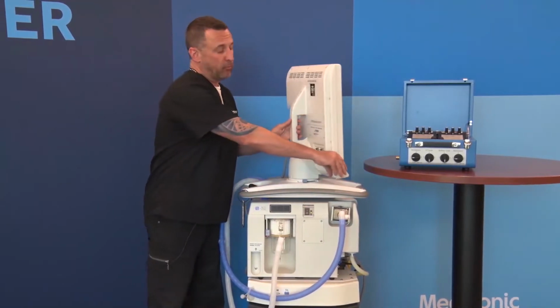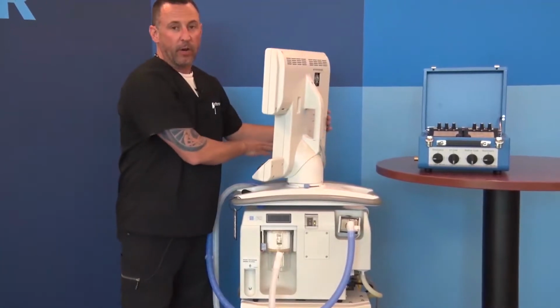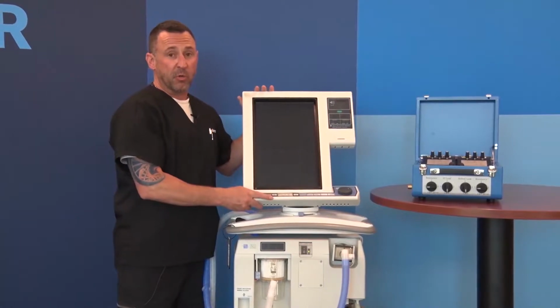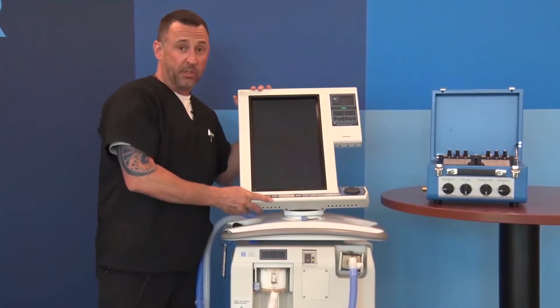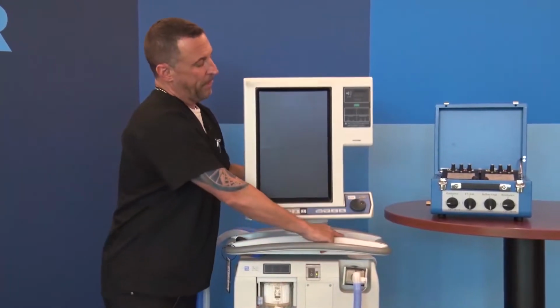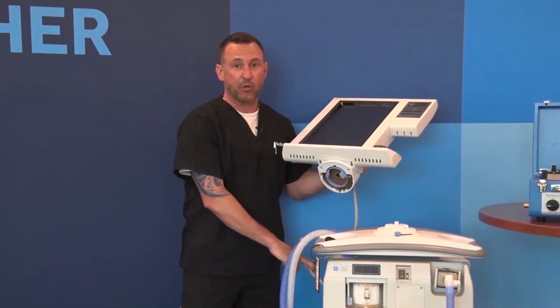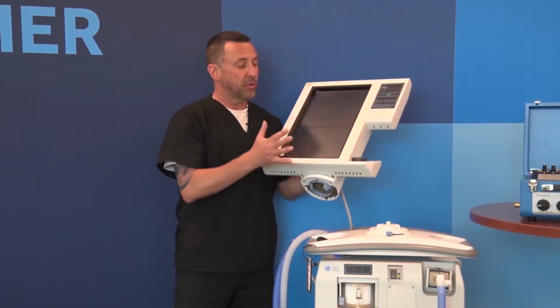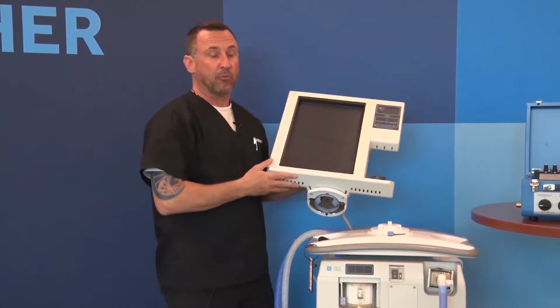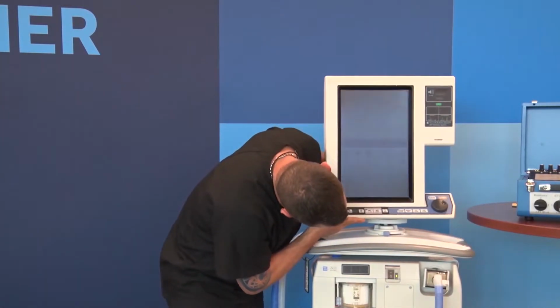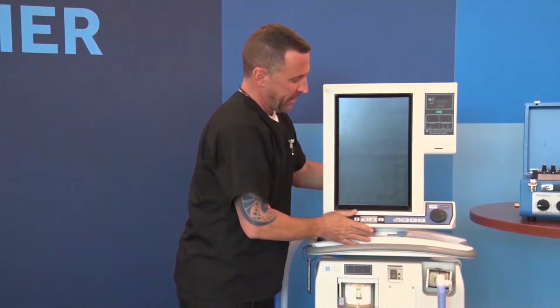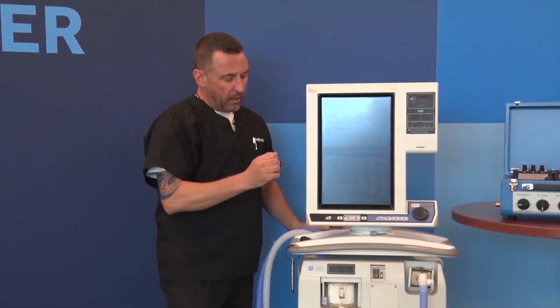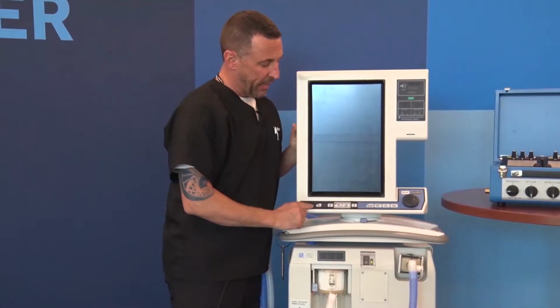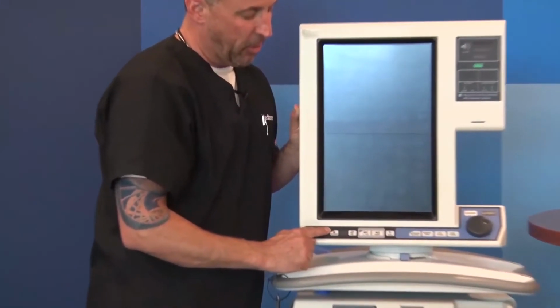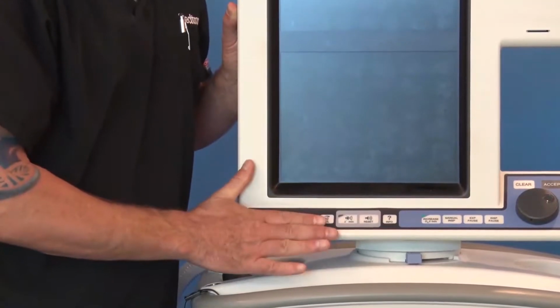The screen, it does move. It rotates 270 degrees, not quite all the way around, but it obviously moves. It tilts upwards or downwards to eliminate any screen glare, or for taller folks and shorter folks. The GUI also can be removed from the cart. We do have a SKU number, a part for a longer communication cable, so that you could operate this ventilator, say, outside of an isolation room or at a distance. Very simply reconnects back to the cart, like so. The screen also has some hard keys, what we call bezel keys, right here along the bottom. I'll talk about those in a little bit more detail when I get the ventilator turned on and go over that.